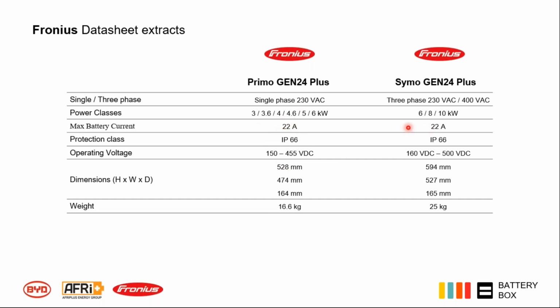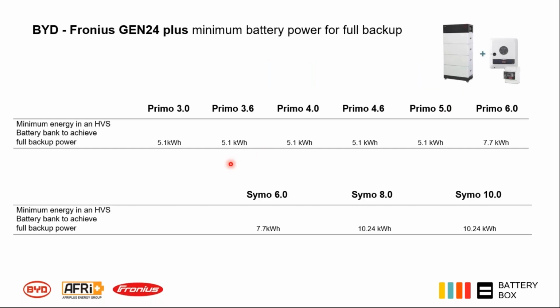And here we can see the maximum battery current is 22 amps, and this integrates very well with the HVS, which has a maximum battery current of 25. And here we can see the Primo and Symo. And here we've got the minimum energy in the HVS battery bank which you need to achieve full backup power. So for instance, if you wanted a full 3 kilowatts of backup, you'd need a minimum of 5.1, but 5.1 is the minimum size of our tower as it is. And then for your Primo 6, if you needed 6 kilowatts of backup, you would need 7.7 kilowatt hours of HVS battery. And a similar scenario here with your Symo, where you'd always need enough battery to supply your backup loads. And the batteries are 1C, so essentially, if it's a 7.7 kilowatt hour battery, you can get 7.7 kilowatts out of that battery at any point in time.